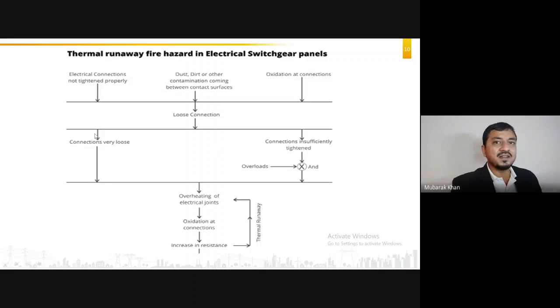If the connections are very loose, it will directly go to the third stage. If the connections are insufficiently tightened and some overload occurs on that load, then this will again go to the third stage. So in both cases, it will go to the third stage. Now, sometimes people say the system has been running for so long and it is not heating, so it is okay, it is good, right?